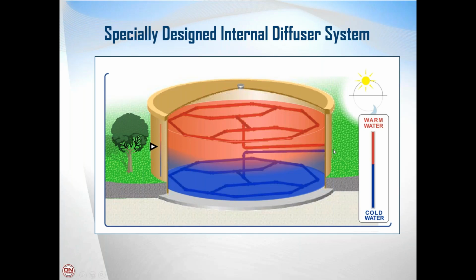So on the right-hand side of the tank, you can see where the piping comes into the tank. The warm water will rise up through the upper diffuser, branch off, and in this case, hit an octagonal ring with slots cut in it. And that's where the chilled water enters and leaves the tank through the upper diffuser, or a mirror image on the lower diffuser inside the tank. And that piping is specially designed to take that flow rate, slow it down to near laminar flow, and spread it out over the cross-sectional area of the tank so that it's not mixing those two bodies of water, so that the cold water stays at the bottom and the warm water stays at the top of the tank.